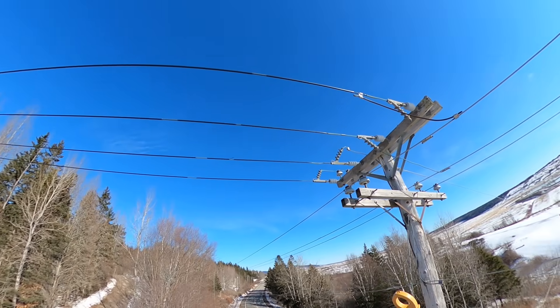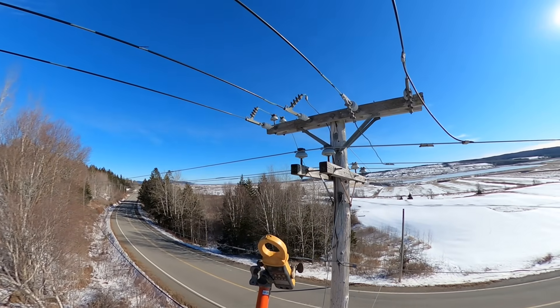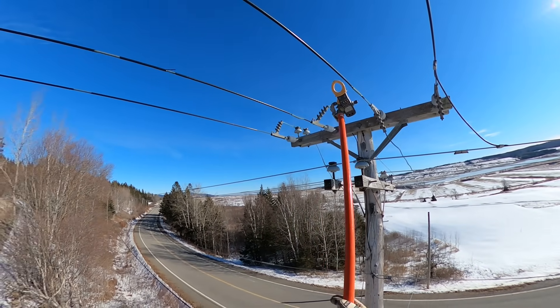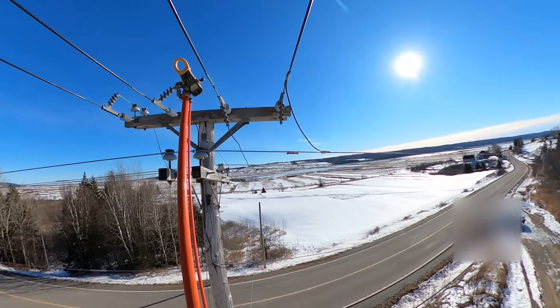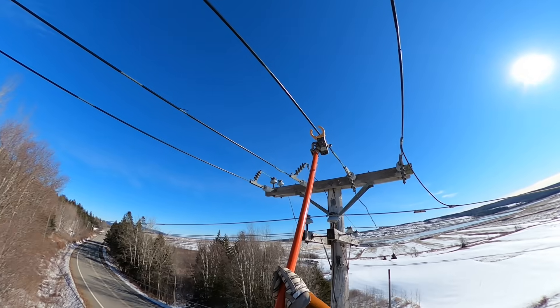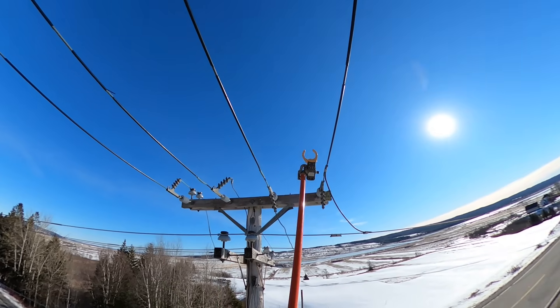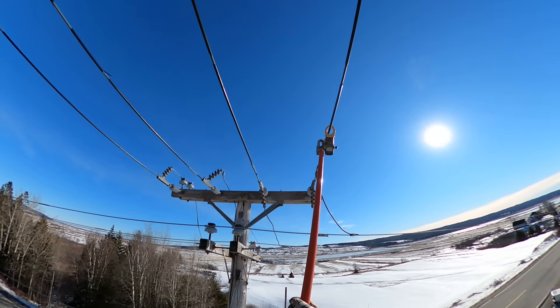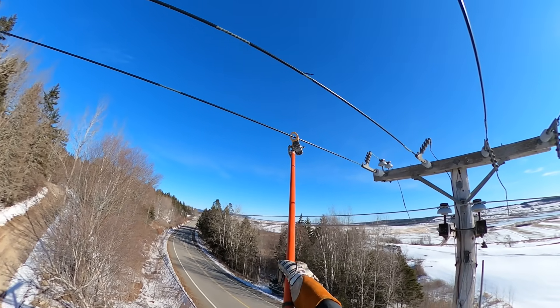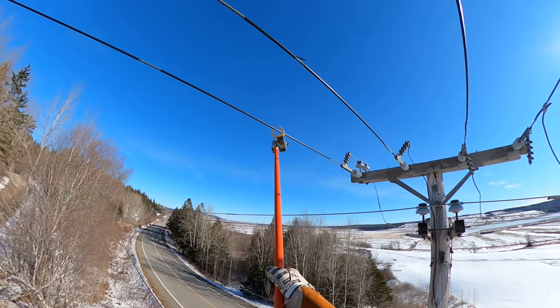This is a four-wire flat construction at 12,470 volts. That's our neutral right there — you can see the copper ground going down and bonding to the neutral. The total amperage on the source right above my head should equal the sum of the left and right side of this pole. We got 96 amps on the center phase, 116 amps, and our last one 112 — so 96, 116, and 112. That's not too bad.